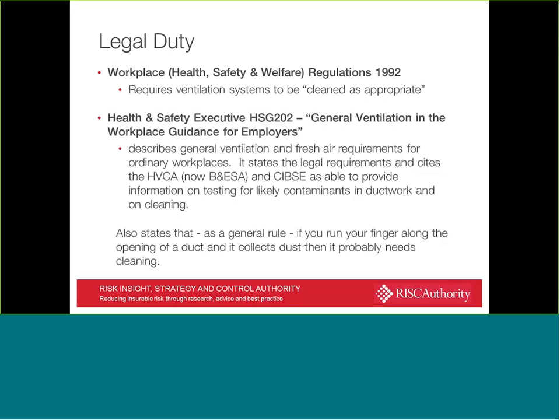The Workplace (Health, Safety and Welfare) Regulations require ventilation systems to be cleaned appropriately. There's a specific HSE document from the Health and Safety Executive called General Ventilation in the Workplace: Guidance for Employers, which describes ventilation and fresh air requirements, which often these systems are designed to use, and also makes reference to the BESA, who are now the Building and Engineering Services Association, and CIBSE, as being able to provide information and guidance on ductwork and contaminants and cleaning.